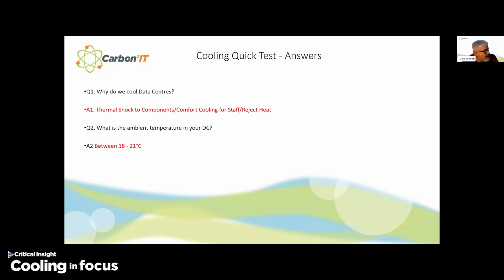What's the ambient temperature in the DC? Between 18 to 21 degrees C. Yes, I know that there are data centers out there that are operating at higher temperatures than that, but this is the conventional; 85% of the enterprise data centers you'll find will still be operating between 18 and 21 degrees. What's your humidity window? Usually it's between 45 to 50% RH, quite a narrow humidity band, and it takes a lot of energy to maintain both 18 to 21 degrees C and also between 45 and 50% RH. And the final question, why? Nobody knows. This is historical. They've been doing it the same way for years, and they don't have access to some of the data center publications. They don't go to the events, so they don't know why they cool it.